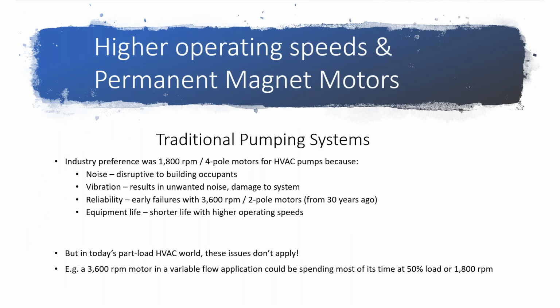So now we move on to higher operating speeds and permanent magnet motors. In order to gain more efficiency out of these pumps, we need to change the way we do things. By lowering the size of the motor, we were able to bring in 2-pole higher speed motors based on the new performance technology. The industry preference traditionally has always been the 1800 RPM 4-pole motors. They're not as noisy, the vibration was pretty decent, and relatively good reliability compared to 3600 2-pole motors from 30 years ago.